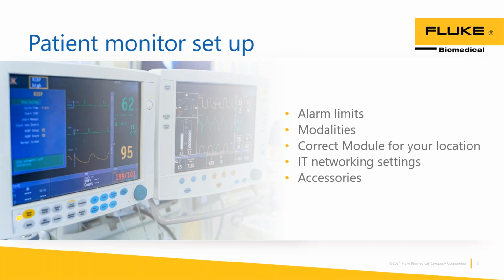So I was thinking about this too, Justin, that when I worked at the hospital as a biomed, sometimes the swapping of modules, or sorry, the monitor itself might have to be swapped out. So it's always important, especially if you're on a call and that work's being done at nighttime, to just again double check that you're using the right modules and accessories, because when you're on call, you're usually the only person there, and you definitely don't want to be called in again for something. You can double check when you're there on site.